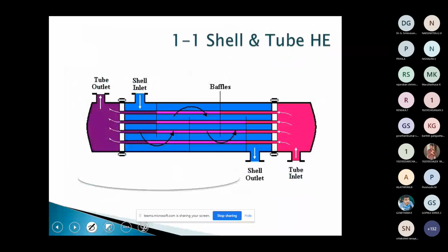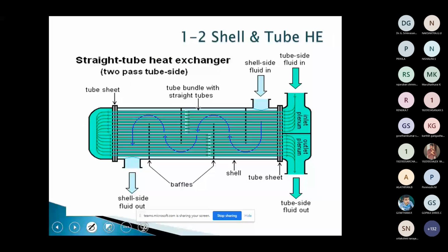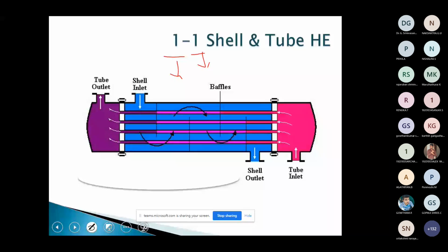Right. Coming to the 1-1 shell and tube heat exchanger, you can see the numbers, 1 and then 1, 2. The first number indicates the number of flows inside the shell side, whereas the second number indicates the number of passes of flow in the tube side. Here the 1 shell means the fluid enters on one side. You can see the shell side entrance is here, it enters here and flows this way, and this is the shell side outlet. Coming to the tube side, it enters here, goes, and then leaves here.